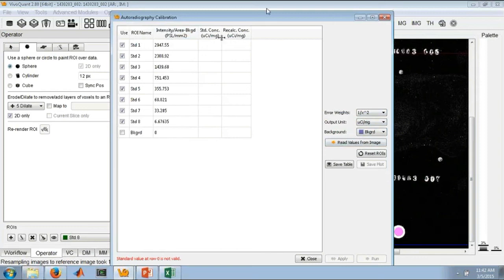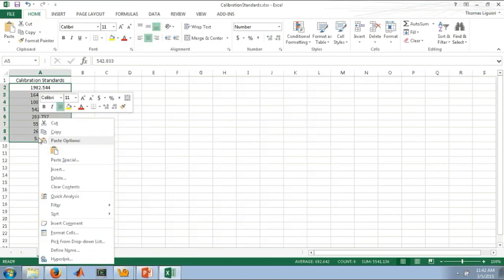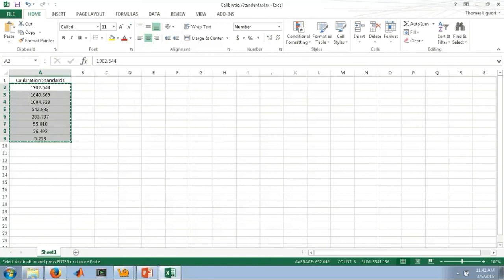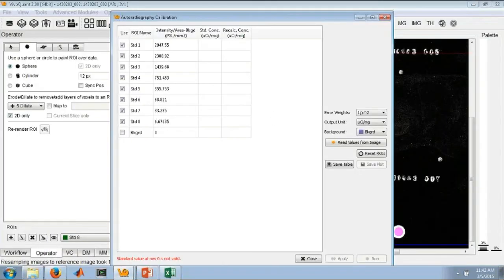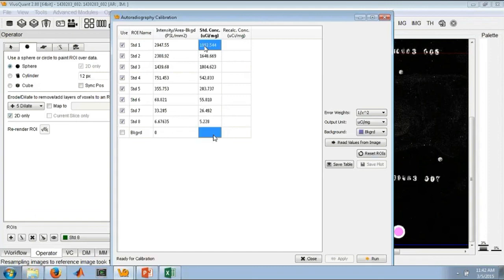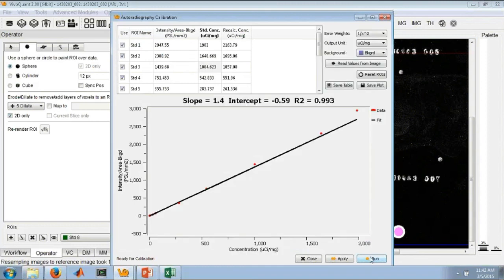We then provide the real world values, or the microcurie values, for instance. And these can be copied and pasted right from an Excel sheet, like so. We can also edit these manually, so if I wanted to change this number, I could do so. Then we say run, and when we do that, it will give us a plot of our curve for the calibration. If we don't like the curve, or we just think we need to change the error weights, we can do that just by running it again.